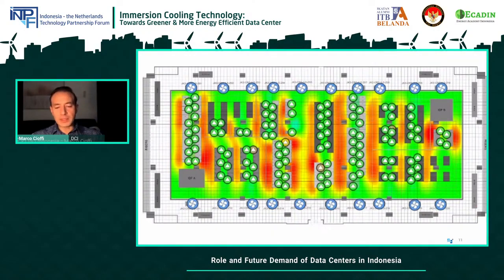We have a system that can monitor the PUE, but can also automatically adjust the fan of the AHU and the chiller unit, depending on the load of every rack. This is quite sophisticated compared to a normal system used in most data centers, where you just set the set point you want your data hall to be, so there are a lot of losses.